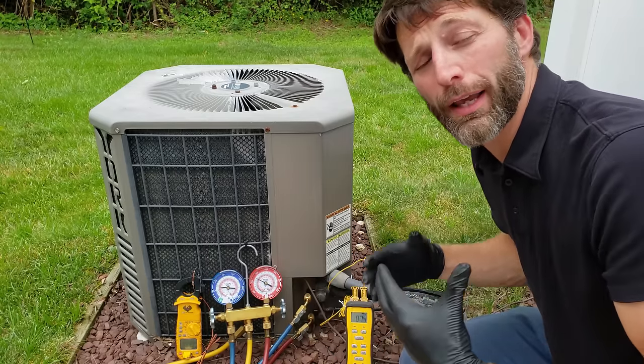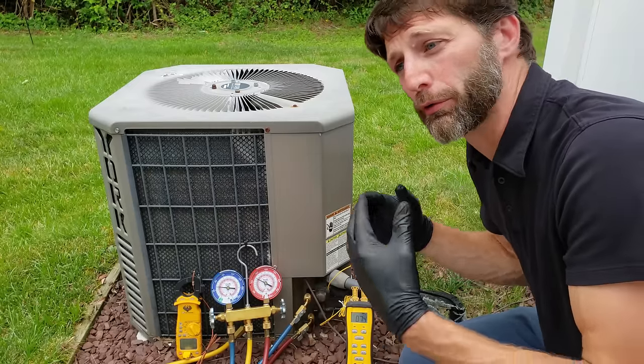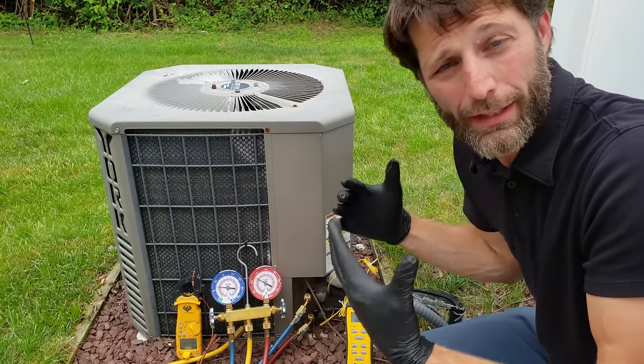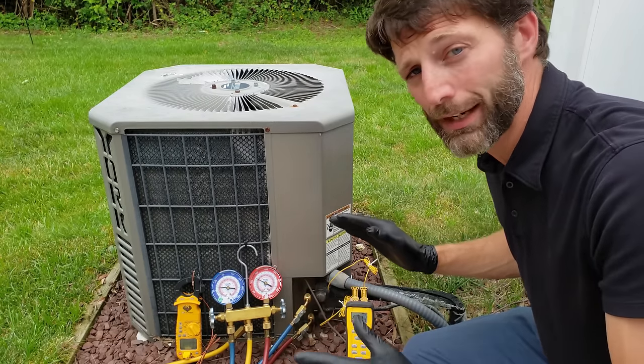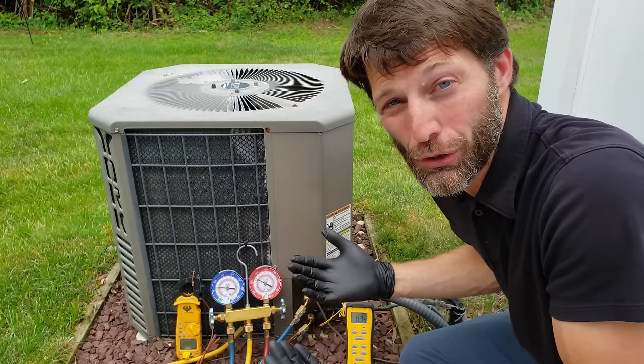I want to describe what Ambient Plus 30 or Ambient Plus 25 means in reference to refrigerant charging. It's a question I get asked a lot and there seems to be a desire for technicians to want to know other charging methods besides the total superheat and subcooling method, so I want to explain what this is and why you shouldn't use it.